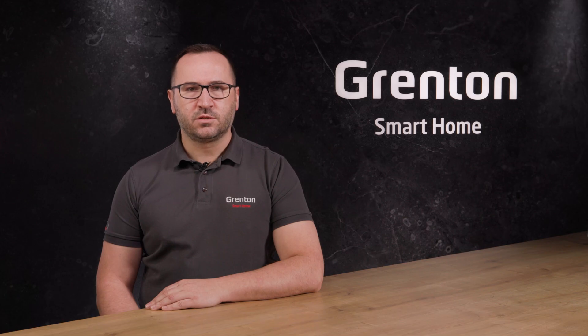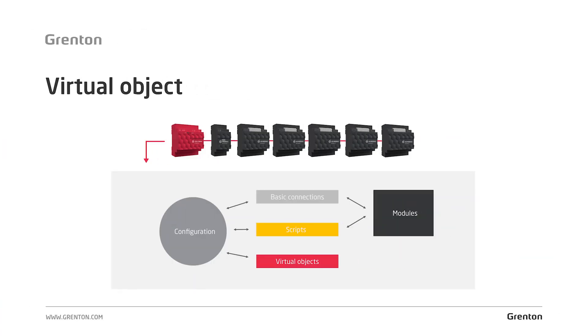To facilitate the configuration process, we have added one more tool to the system, and these are the virtual objects. Generally and simply speaking, virtual objects are ready-made logical blocks which were created inside the system's logic. These blocks, just like the inputs and outputs in the system, have their own features, methods and events. From the configuration point of view, we will handle and use them exactly as if we were using physical inputs and outputs in modules, but they do not have their physical duplicate. This means that to use a given virtual object, we do not need to add an additional module — it is simply embedded inside the logic of a given device, a given object of CLU class.